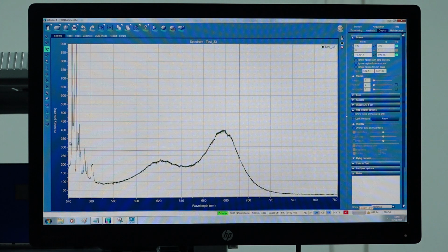Again a word of caution here: care must be taken that the range selected should not include the 532 nanometer spectral position, because the green laser that we are using is 532 nanometer. Even though we are using an edge filter, a large intensity can pass through the filter and that can damage the CCD detector.